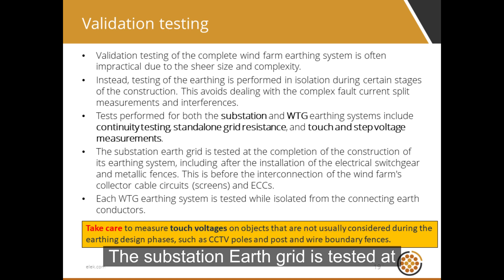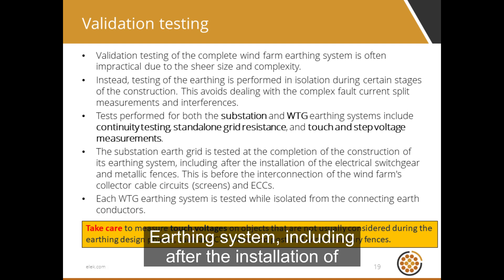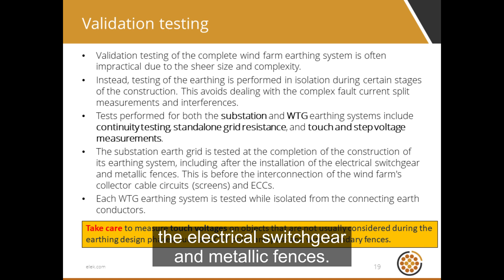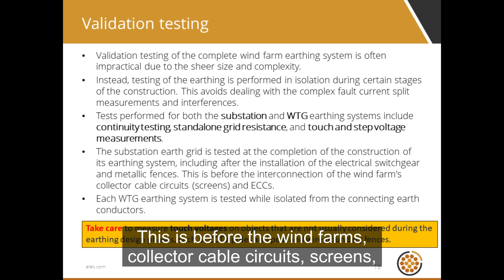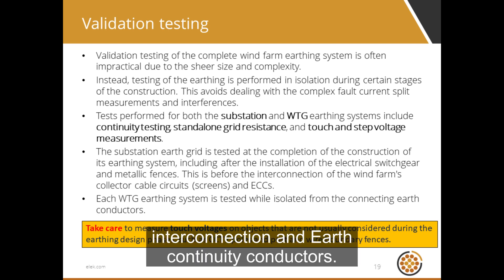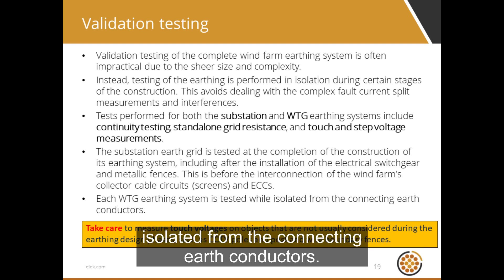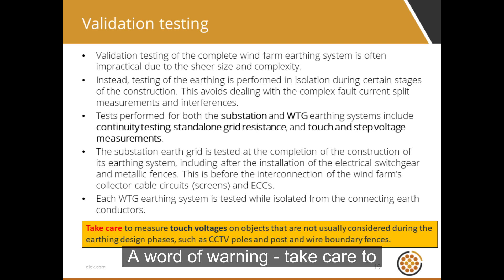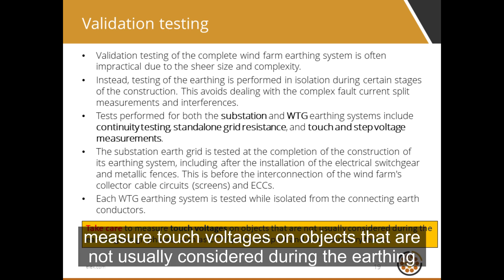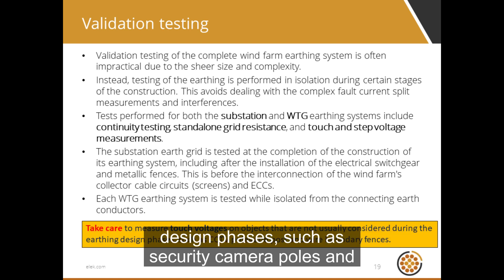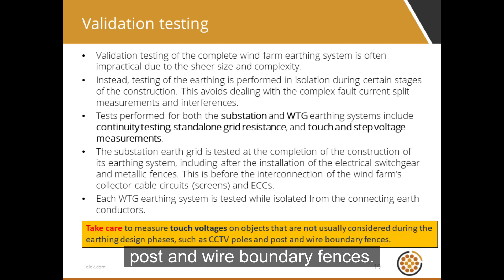The substation earth grid is tested at the completion of the construction of its earthing system, including after the installation of the electrical switchgear and metallic fences, and before the wind farm's collector cable circuits, screens, interconnection, and earth continuity conductors. Each WTG earthing system is tested while isolated from the connecting earth conductors. Take care to measure touch voltages on objects not usually considered during the earthing design phases, such as security camera poles and post-and-wire boundary fences.